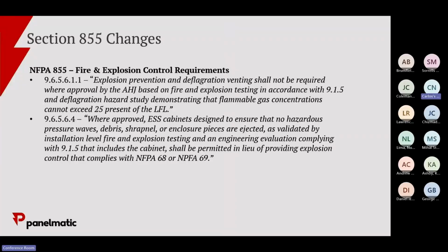What these codes are trying to do is basically get the LFL, the lower flammable limit, and try to keep that VOC level down. Because obviously what started and sparked a lot of this, if you remember the real world example we used in the first case, the battery energy storage plant in Arizona, the firefighters opened the door and it exploded. What ended up happening is these batteries are emitting hydrogen before they go into thermal runaway.